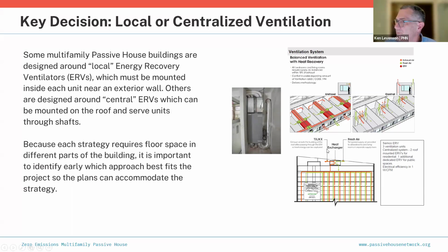In this building, which is Cornell Tech, they looked at two ways of doing it. In one, every apartment had its own ventilation system in the ceiling - you see in the little section here, unit up, then ducted, with all this mechanical system happening around the perimeter to get back to the kitchen and whatnot. What they ended up doing was putting a big central heat exchange ventilation unit up on the roof, with risers going down through the building.